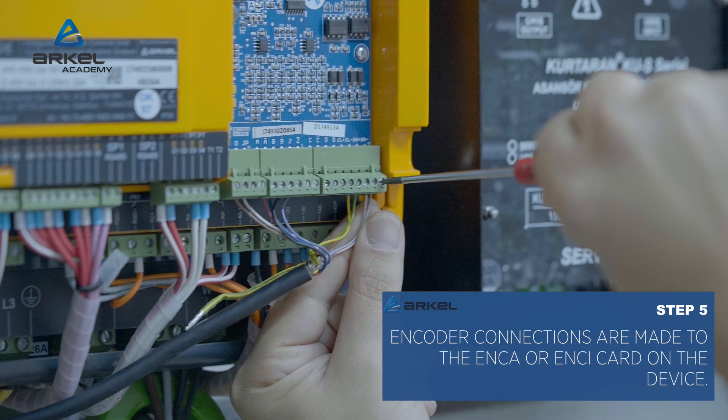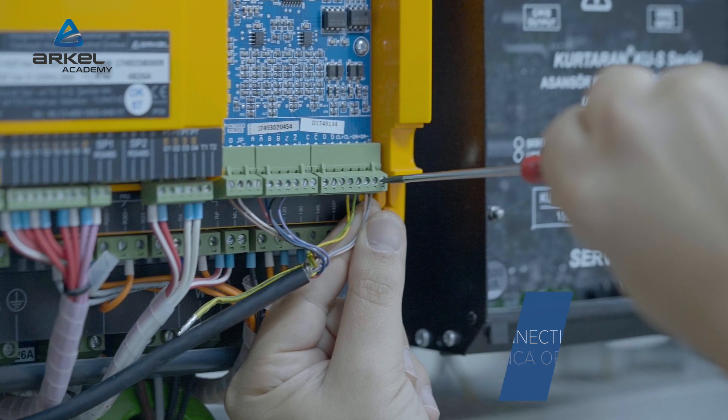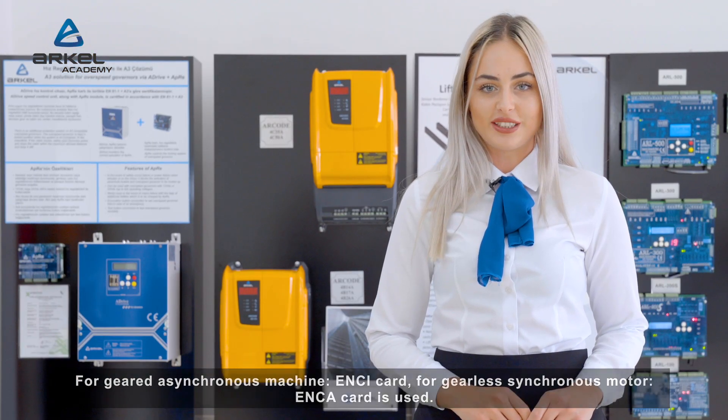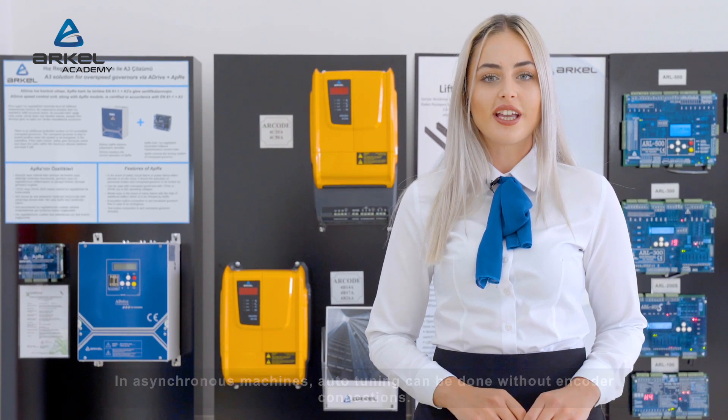Encoder connections are made to the ENCA or ENCI card on the device. For geared asynchronous machines, the ENCI card is used. For gearless synchronous motors, the ENCA card is used. In asynchronous machines, auto-tuning can be done without encoder connections.